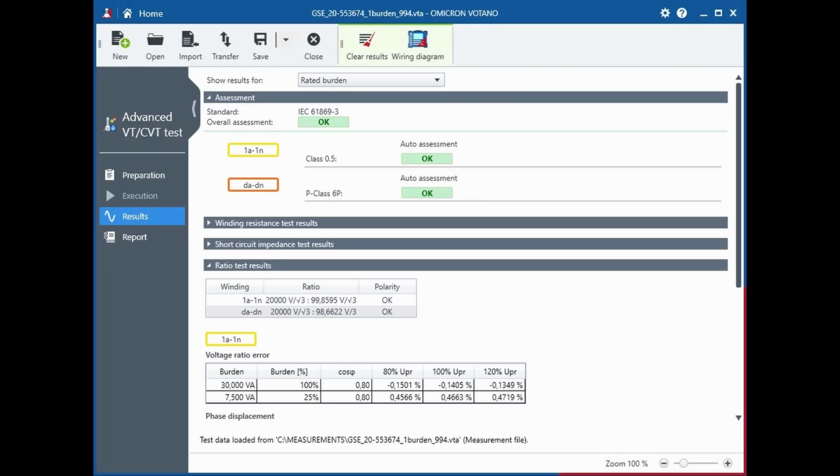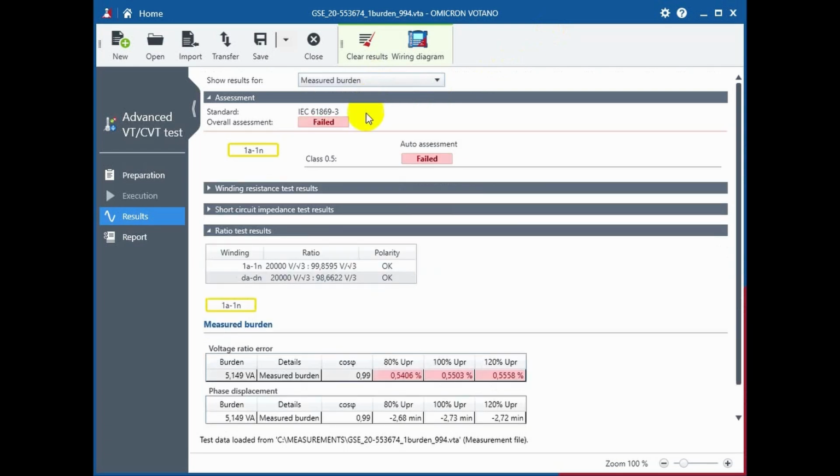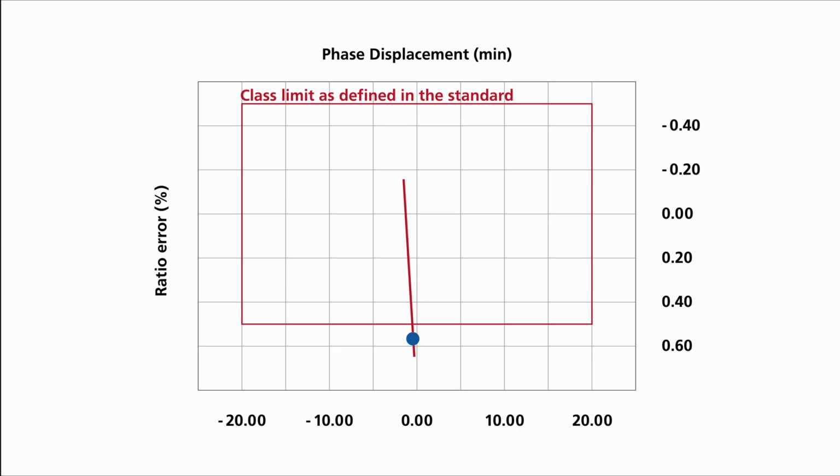After replacing the secondary devices, your voltage transformer will still be rated with the nominal load, but may fall out of the accuracy class with the measured load if these new meters or relays represent a lower load than the load that was used in the design of your voltage transformer. If you want to continue using your voltage transformer, you must increase the load so that the connected load is again between 25% and 100% of the nominal load.